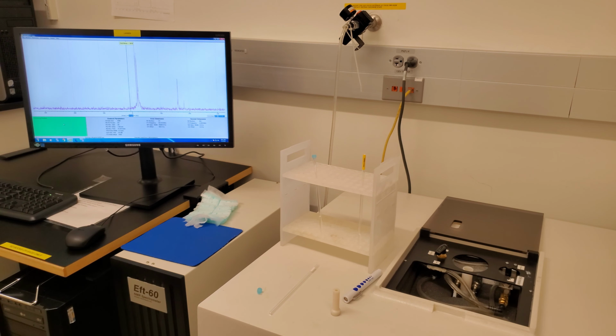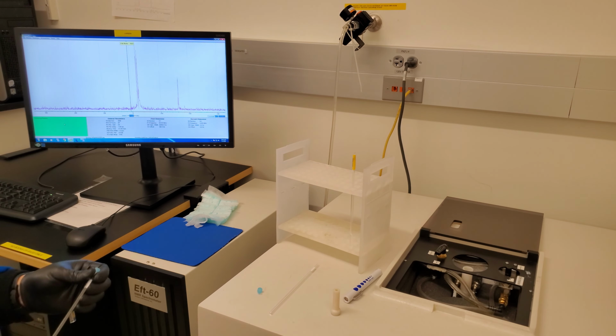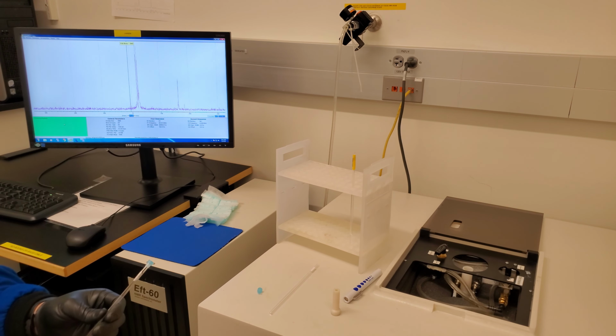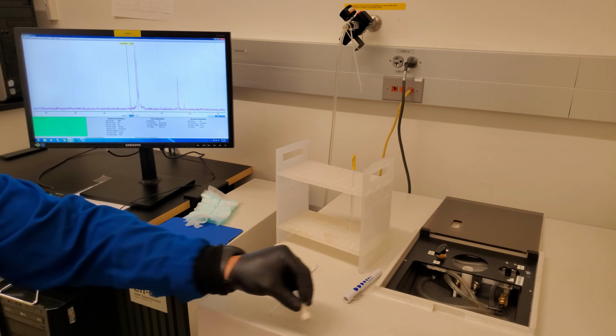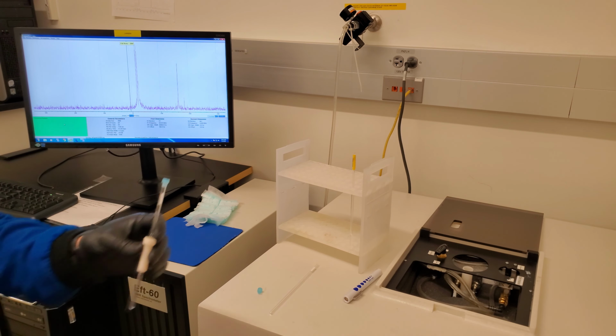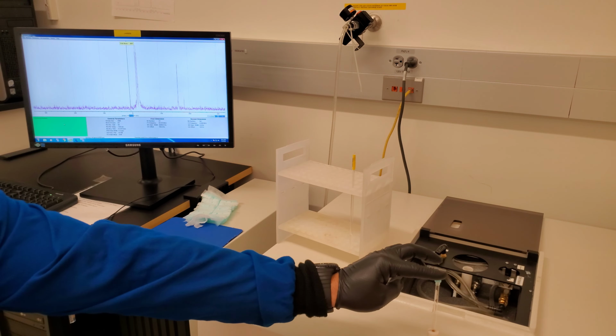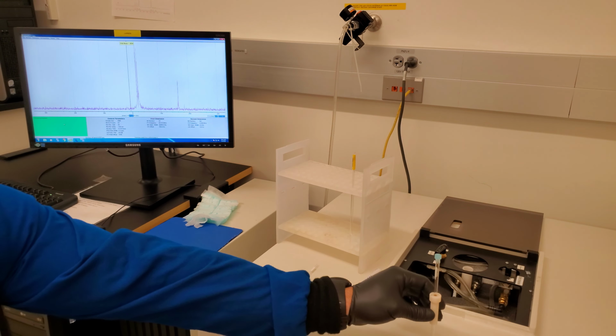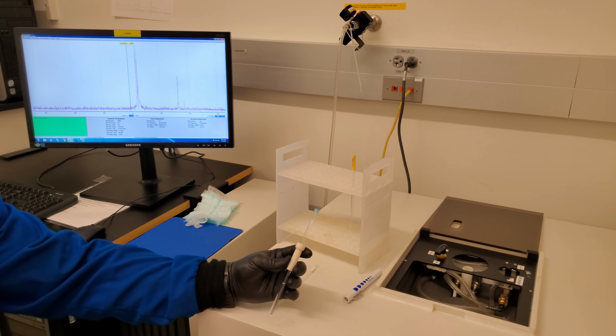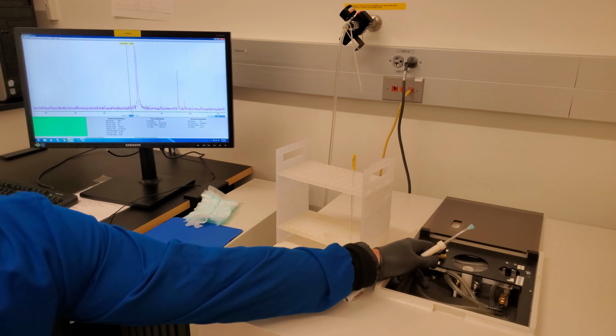Another issue that can arise is that the spinner is not spinning. To troubleshoot this problem, take the NMR spinner out of the magnet. Wipe down the NMR tube with a Kim wipe. Ensure that the NMR tube is sitting in the NMR spinner at the correct height by using the gauge on the front top of the magnet. Ensure that the NMR tube and spinner are settled at the bottom of the probe before turning the knob from spin to non-spin.